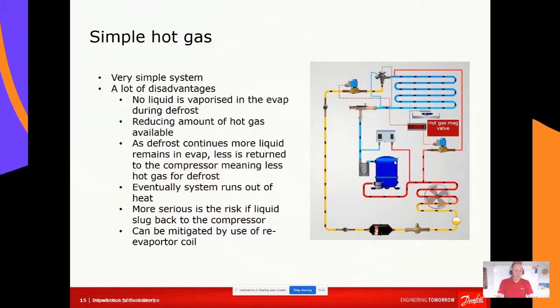The other bigger issue is the risk of liquid slug back to the machine. Now you can see here we've got a nice big suction accumulator or slop pot, as I've called them in the past, and that hopefully protects our machine against liquid because a compressor is a vapor pump, it's not a liquid pump.